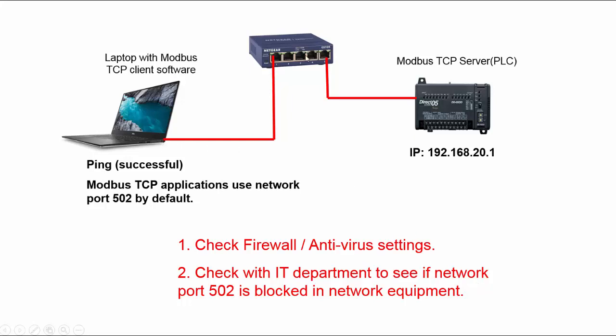That is network equipment where Modbus TCP packets have to traverse. Usually when they check these two — the firewall and the network equipment — they'll find that port 502 is blocked in one or both instances, and once it's unblocked, Modbus TCP communication takes place just fine. So that's the number one Modbus TCP issue I get emails about.